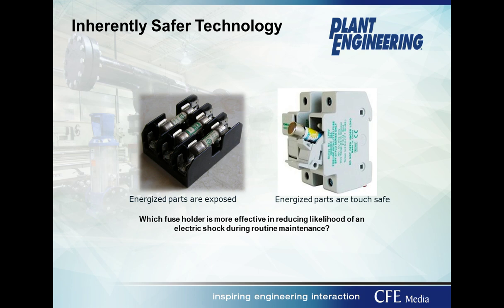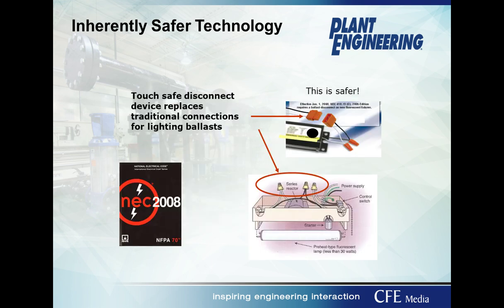The fuse block on the right is designed with all the energized parts shrouded or covered, so that if you were working on or near that fuse block, or even wanted to change or replace a fuse, it can be done without exposure to electrical hazards. So the question here is, which fuse holder is more effective in reducing the likelihood of an electric shock during routine maintenance over its lifetime? This could be in place for 25, 30, 40 years, maybe even longer.